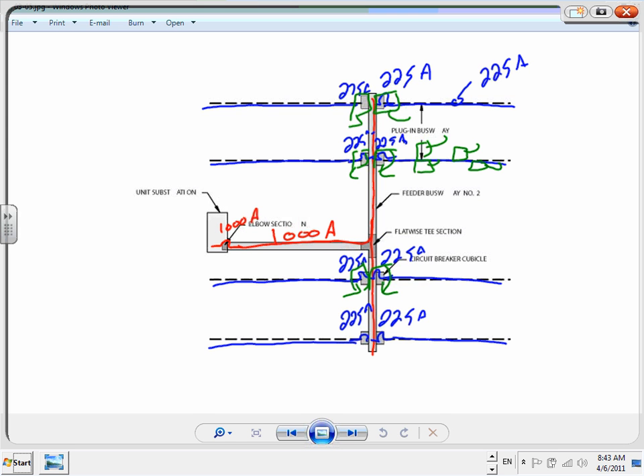We're going to circuit that to the mechanical equipment then? These buses, based on our requirement, are coming directly from the switchgear. Okay. So we're not going to circuit from the disconnect to the mechanical equipment? You mean, am I going to circuit the equipment to the disconnect? If that disconnect goes to your air handling unit, are you going to circuit it to the air handling unit, or just to the panel? Thank you. First, I'm talking about the owner equipment, so the air handling unit is not part of this discussion. I'm coming to that one. Very good point. I'm talking here, guys, of the owner equipment. These are the welders and all this good stuff.